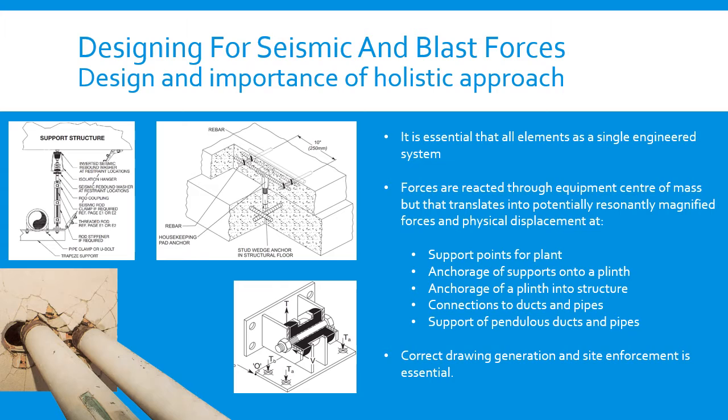It's unlikely that, especially in countries like the UK, contractors will be familiar with these processes and correct installation of equipment. Having an experienced supplier on board from the outset is important, and equally, site enforcement of the installation allowed for. Small errors like oversized holes, tension cables or pneumatic spring mounts can result in failure.